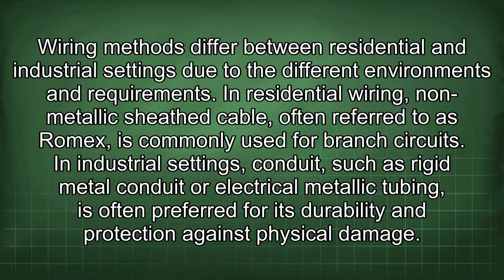Wiring methods differ between residential and industrial settings due to the different environments and requirements. In residential wiring, non-metallic sheathed cable, often referred to as Romex, is commonly used for branch circuits. In industrial settings, conduit, such as rigid metal conduit or electrical metallic tubing, is often preferred for its durability and protection against physical damage.